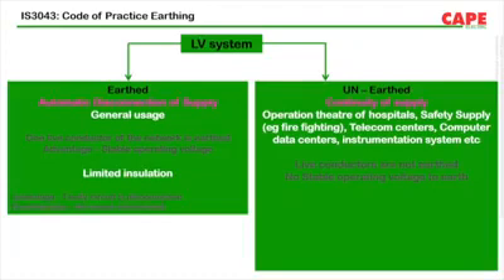Unearthed system, or IT system, ensures continuity of supply during first fault. Unearthed system is recommended for operation theaters in hospitals, safety supply for firefighting and life-saving equipment, telecommunication application, instrumentation and control, and BMS. Depending upon the application, user can opt for one of these two systems.